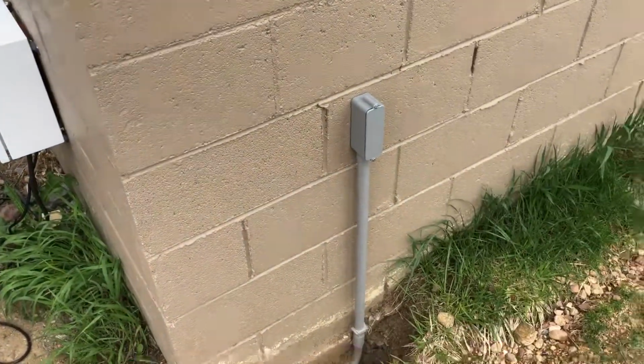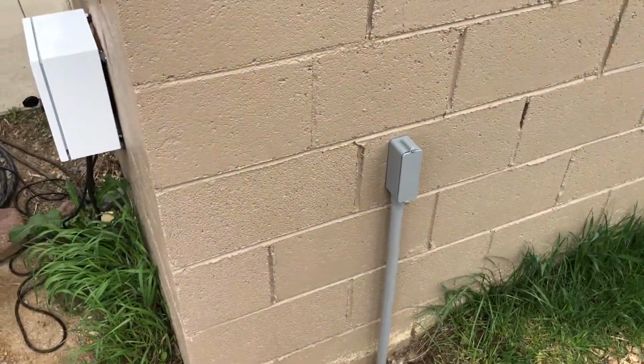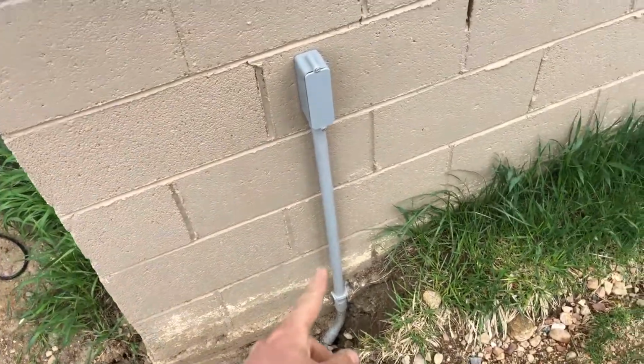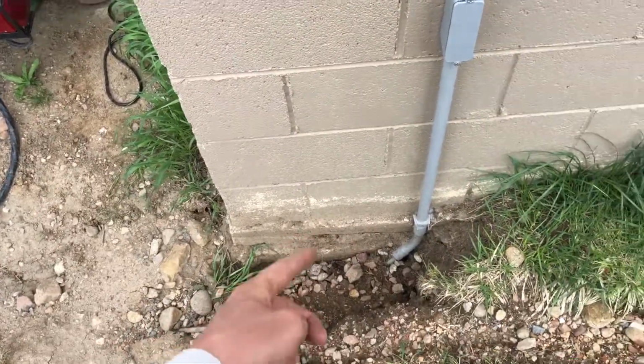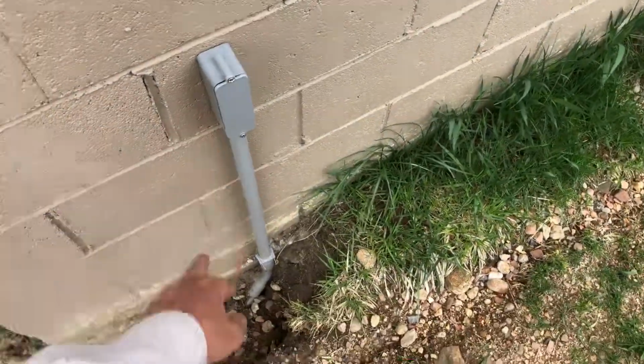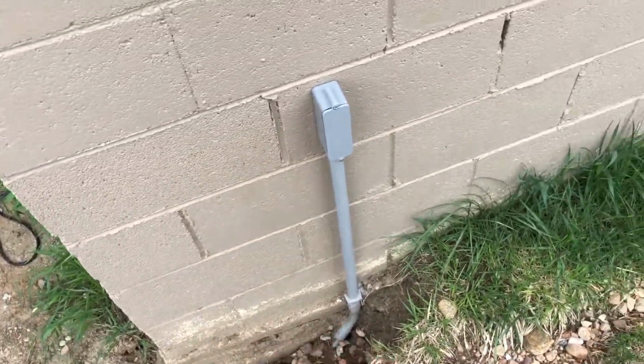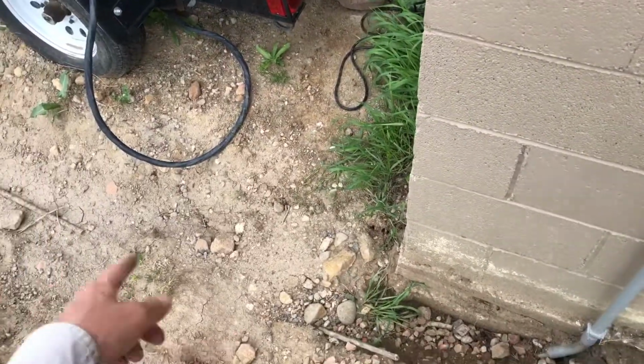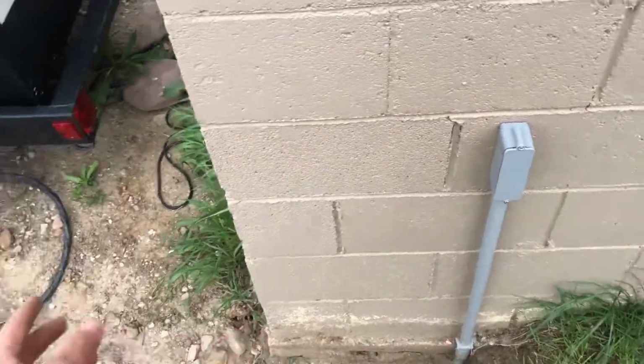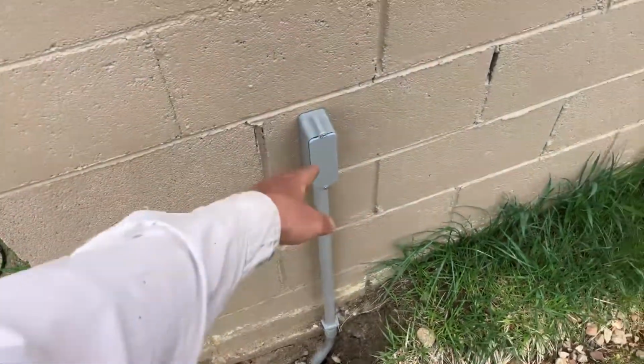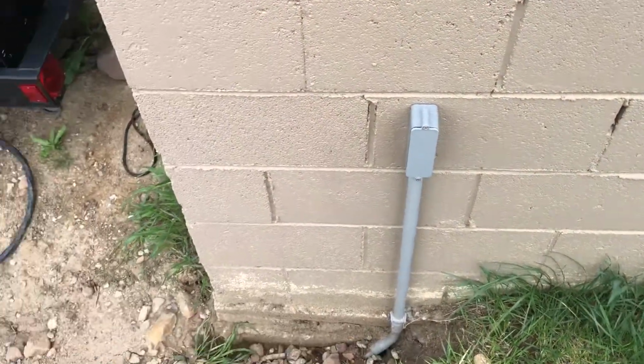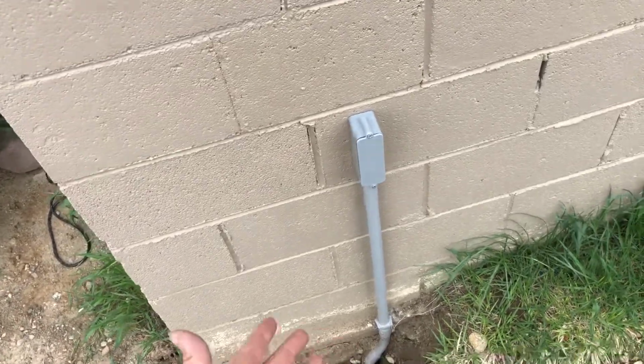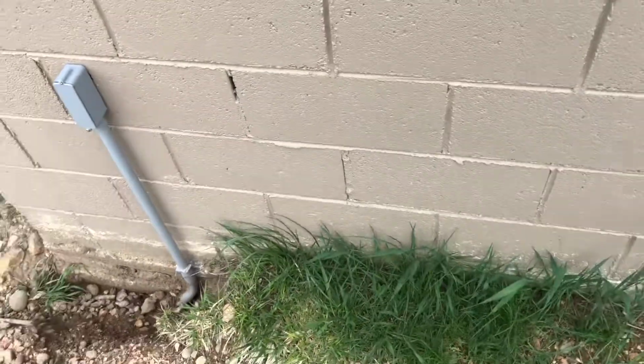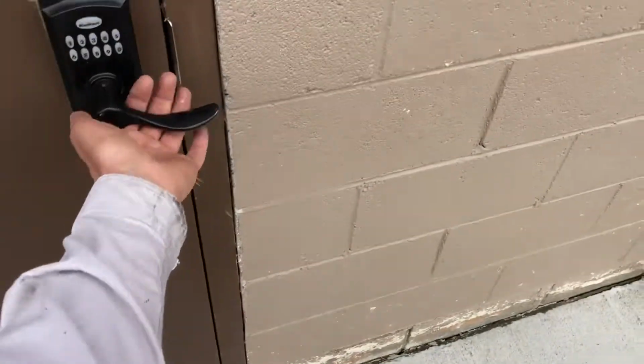And this house is adjacent to another structure owned by the same client. And so we ran a 10 gauge, or the client rather ran this, a 10 gauge 4-wire type UF cable underground, and it was 500 feet to this location here. Hence the battery and inverter, because you can't run an entire house on 500 feet of 10 gauge cable. So in order to make that system work, we set up a charger.